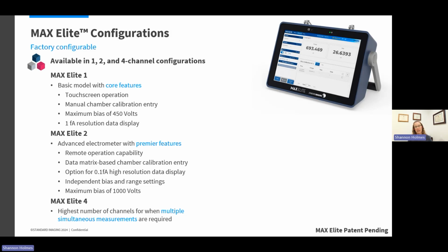There's an option on these electrometers as well to show an additional digit of resolution, to show a 1/10 of a femtoamp in the high resolution data display, if that's something that you are interested in or want for your measurements. You don't have to if you don't like to see the extra digit cluttering up the screen. The 2-channel electrometer has independent bias and range settings for the 2 channels, just like with our SuperMax electrometer. And the maximum bias there is 1,000 volts.